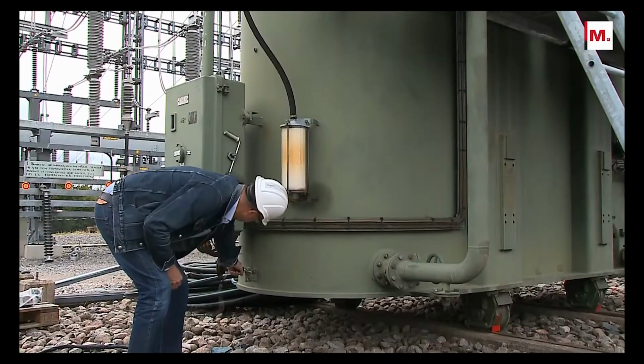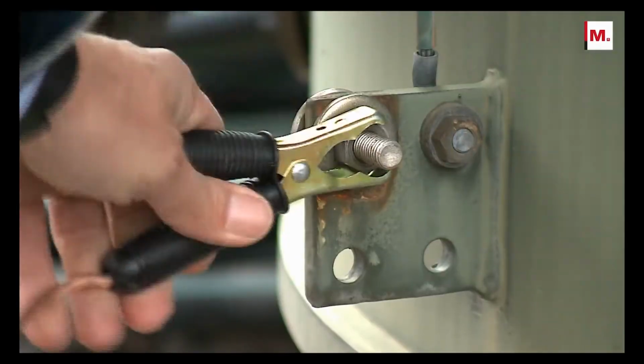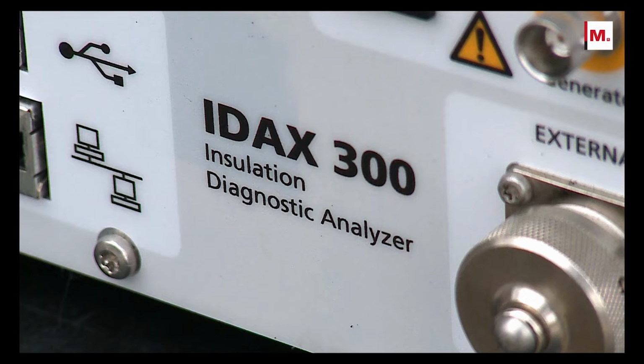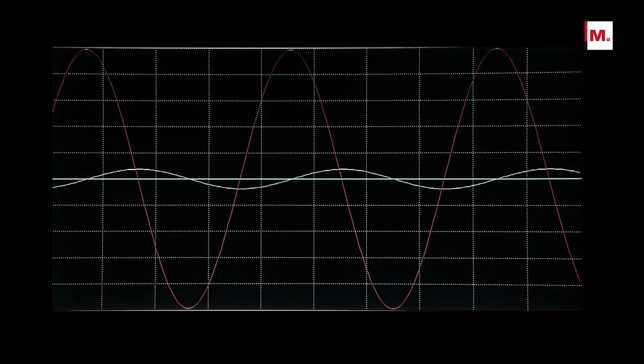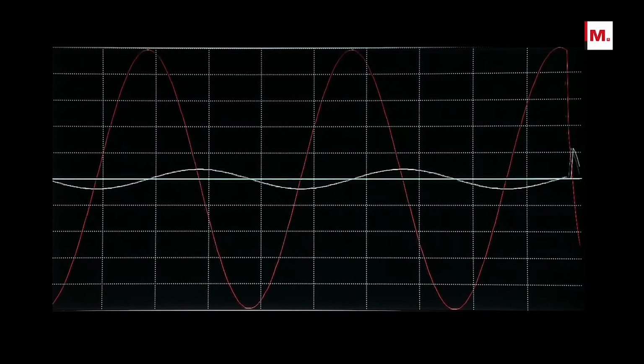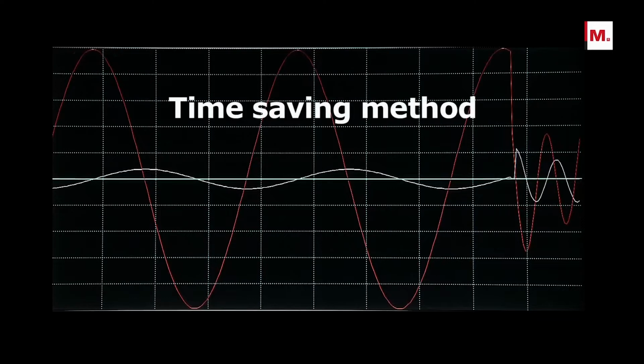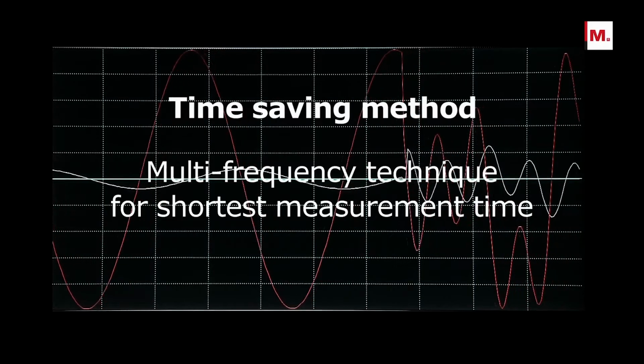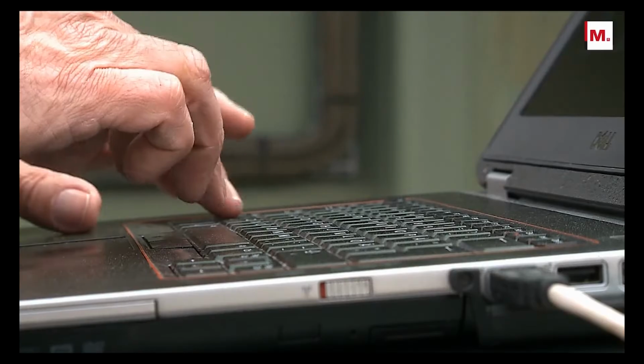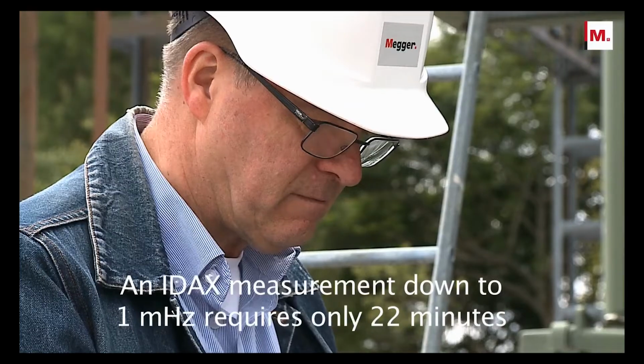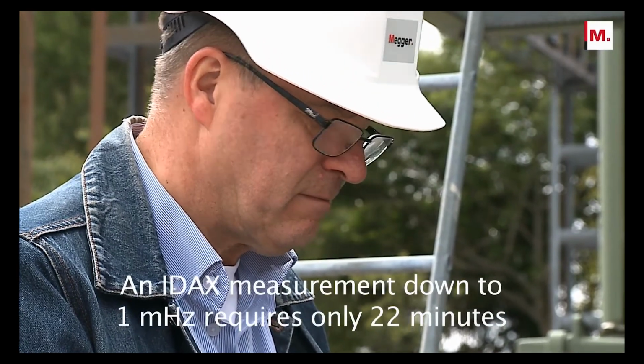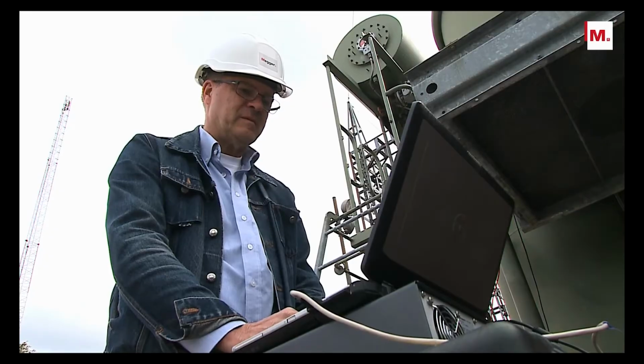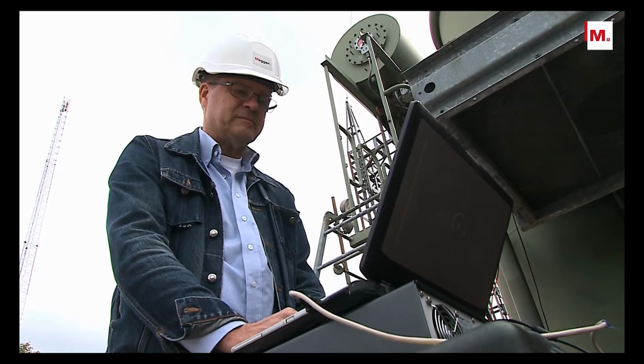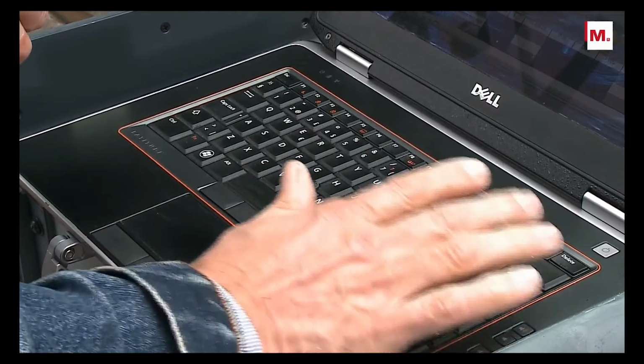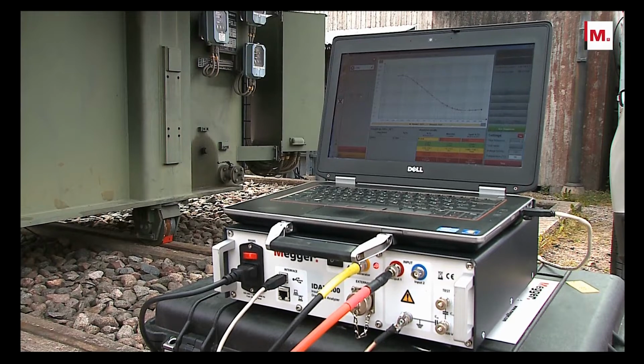Measuring dielectric response at very low frequencies takes time. In the new IDAX, this issue is addressed by introducing a new and unique method where the test signal at low frequencies contains a combination of frequencies. This method significantly reduces the measurement time in the low frequency range and, consequently, the total measurement time. As an example, an IDAX measurement down to 1 mHz requires only about 22 minutes, the fastest DFR test available, without compromising the accuracy and reliability of the frequency domain measurement technique.